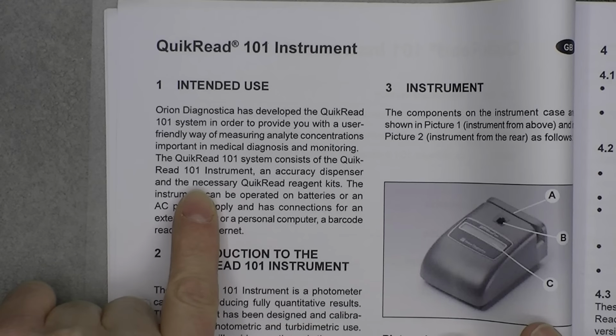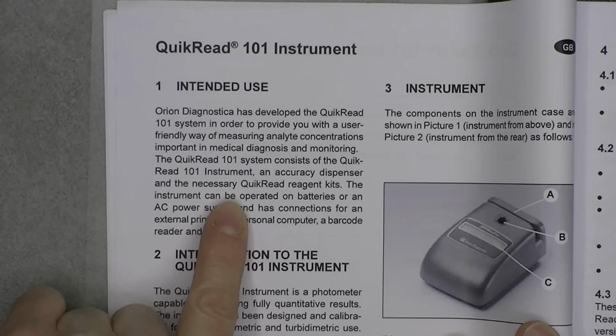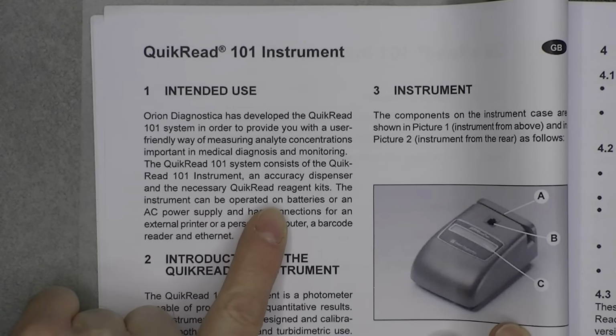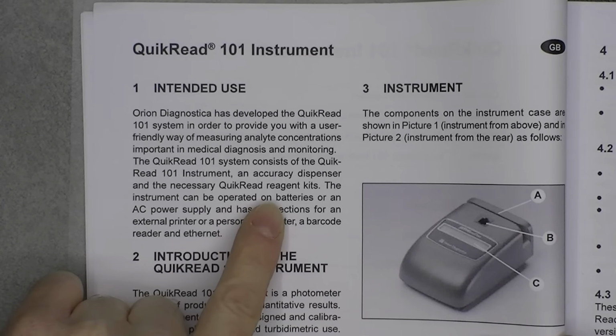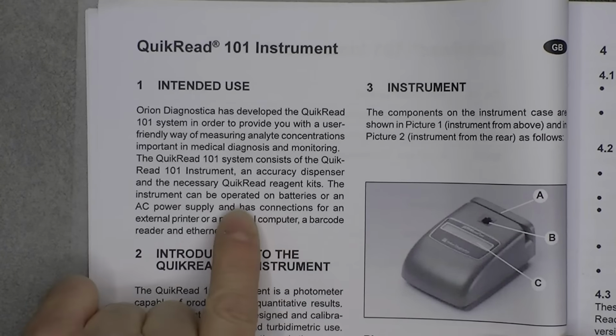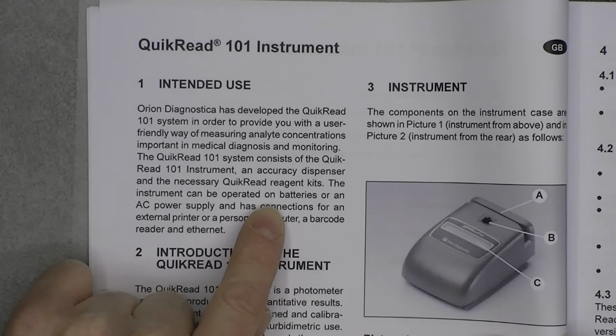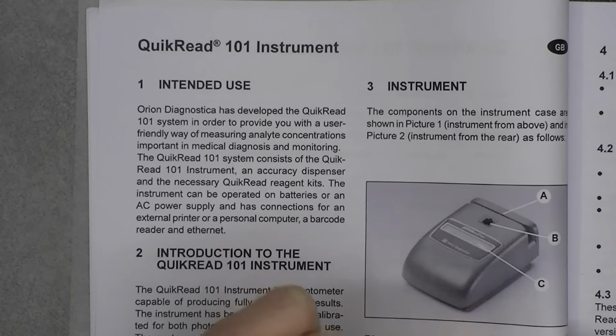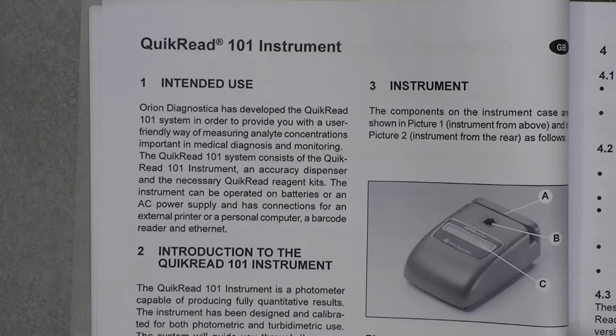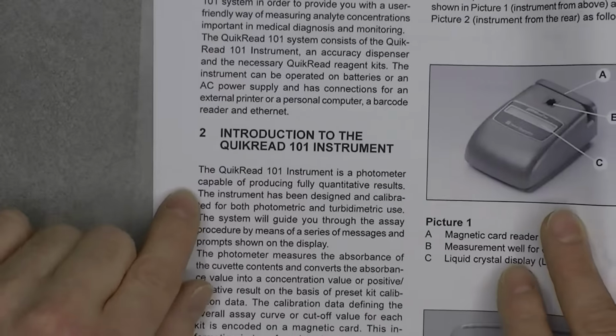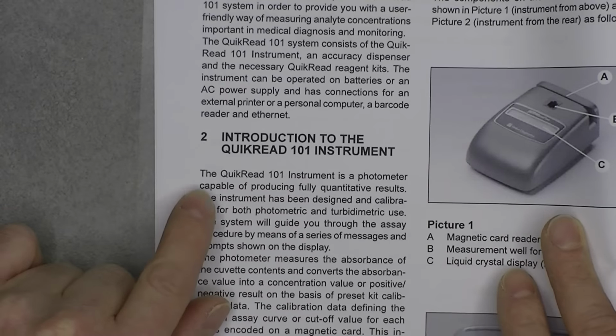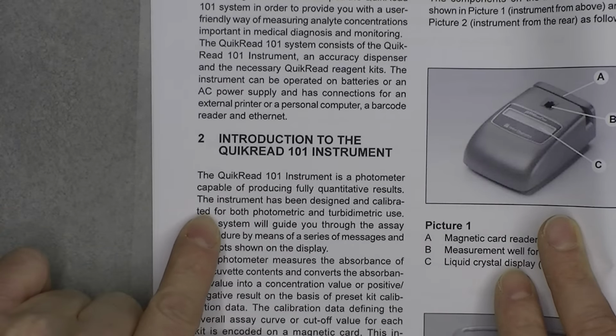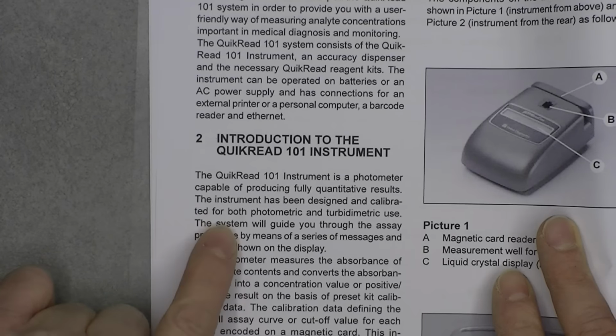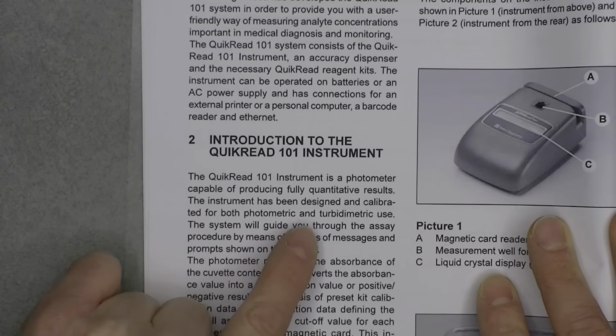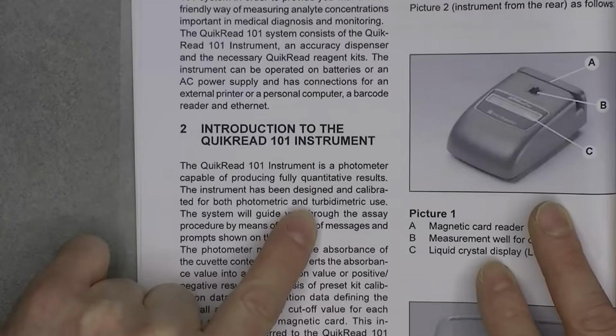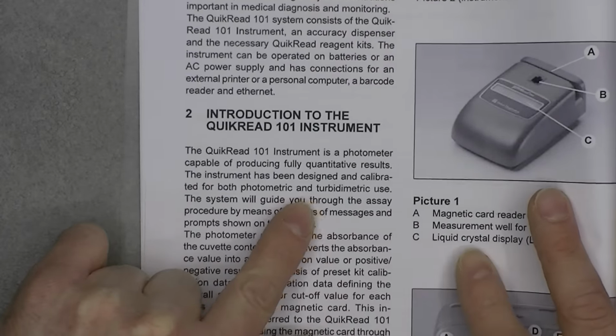It consists of the instrument itself, an accuracy dispenser and the necessary QuikRead reagent kits. So from what I understand, each kit comes with what they call a cuvette for analysis and reagent, and one matching magnetic card, which will configure the instrument for what you want to do. So it is a photometer capable of producing fully quantitative results. It is calibrated for both photometric and turbidimetric use. So this is worth checking in Wikipedia, I believe.